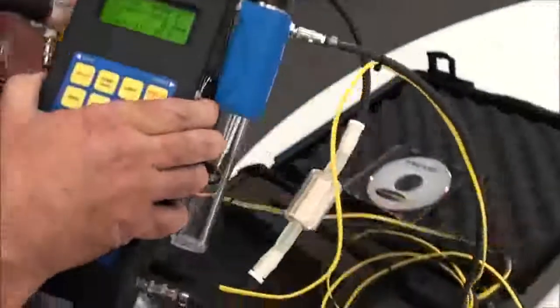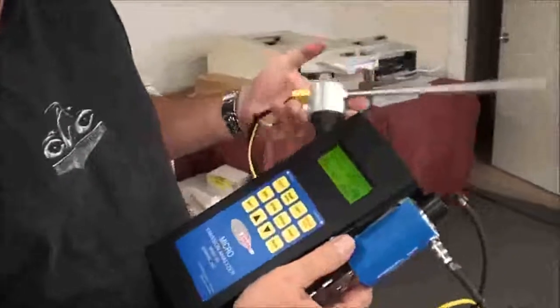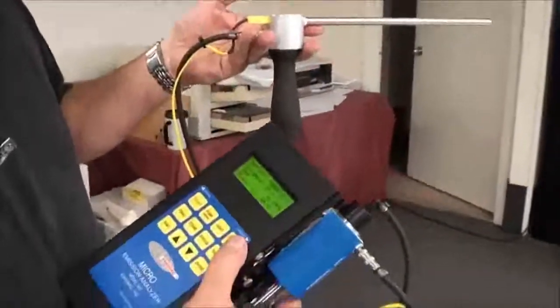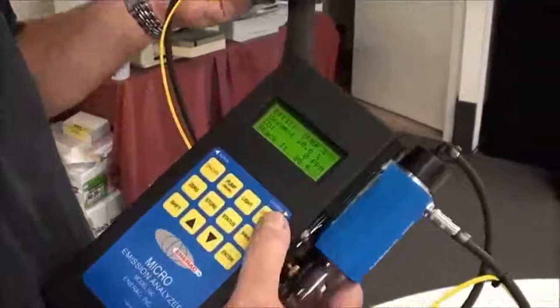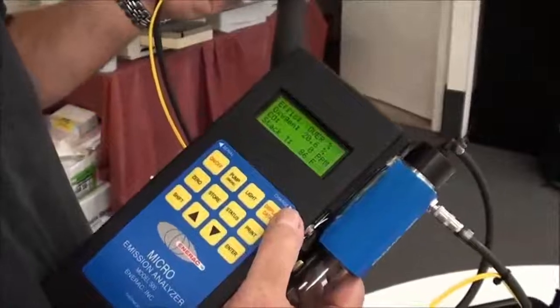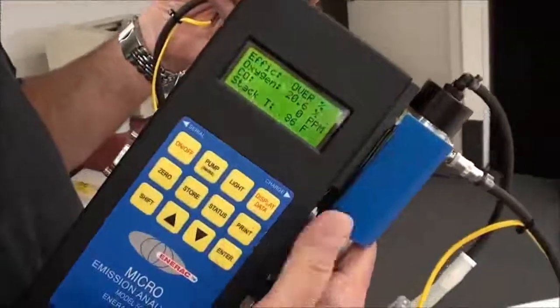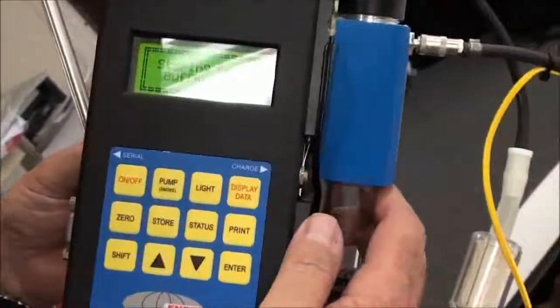What you'll do is take the unit out to your source, insert the probe in the stack, watch the readings, wait till they stabilize. Once you're satisfied that you've got good readings, or you've got the readings where you expect them to be, or you've made any changes to the equipment, and you watch the display and everything is where you want it to be, you have several options at this point. You can either print it, you hit the print button, and it prints out the top, gives you a hard copy, or you can hit the store button, it stores it internally. So once you've done that, you hit enter, and it stored the data.